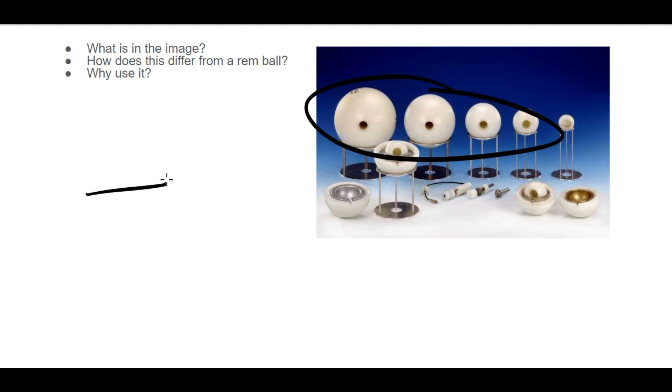Let's do a quick little drawing. We have this detector that is going to detect a gamma ray, but that gamma ray needs to be created by these Bonner spheres. You have this detector surrounded by these polyethylene spheres. What these are going to do is moderate the high-energy neutrons to lower energies.